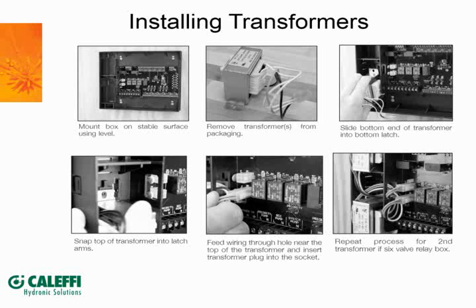The 3 and the 4 zone come with a single transformer, but they are expandable. So if you had, let's say, a 3-zone unit and you had somebody else's big, power hog zone valve in there, you could add another transformer and plug it in. They're both in parallel, so now you'd have 80 VA to supply out to those 3 zones. And obviously, if you had to replace a transformer, it makes it easy. You don't have to drill out any pop rivets or anything like that. You just take a screwdriver and slide those little tabs over. You can rotate it out of there and replace it, and it's really serviceable.